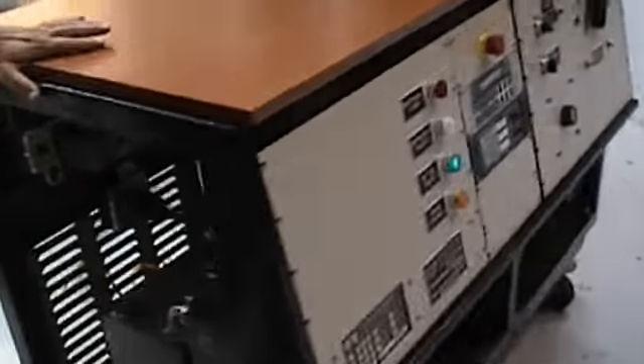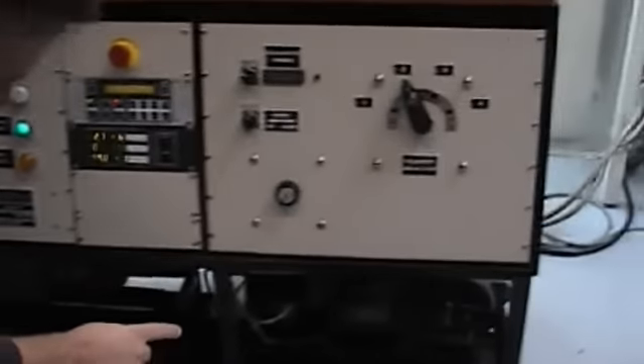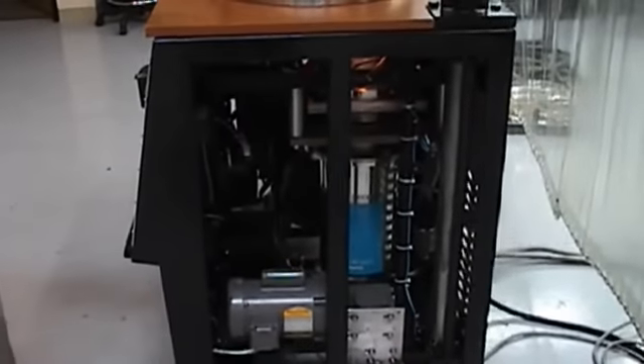What you hear operating now is the cryo pump in the back, and we'll go over to the other side to take a look at that. Out the front of the machine, as I had mentioned earlier, we do have one section here that will be a constant power, and that is marked on there, live power, 208 volts, and it is a constant even with the stop switch turned off. This is our 2 kVA transformer located in the front. This is a low voltage transformer. It does have some taps. We're operating on a 5 volt tap right now. If you needed to change the tap, you would have to physically change it.